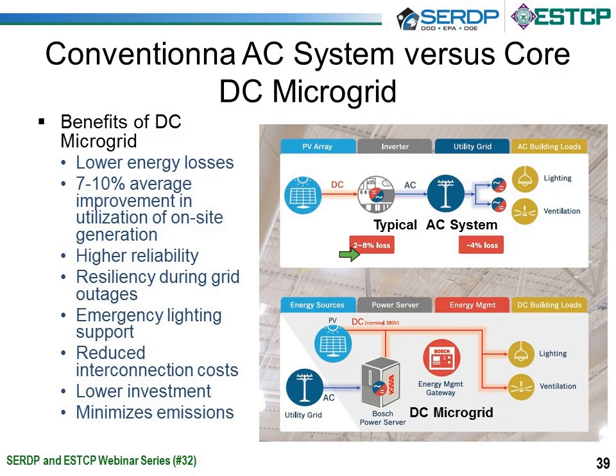Modern inverters talk about having 98% efficiency. That's at or near their peak power. But many times it's cloudy out or it's not the middle of the day, and they have a significantly higher loss. So if you add these two losses together and you average it over weather conditions across the year, what we found is you get about a 7-10% loss of your solar energy.